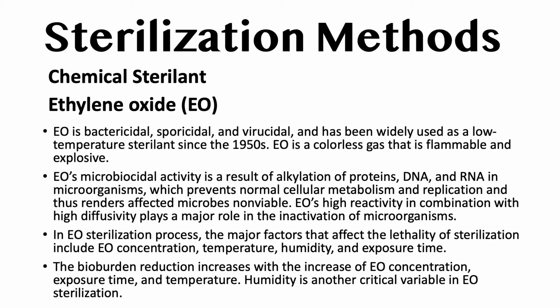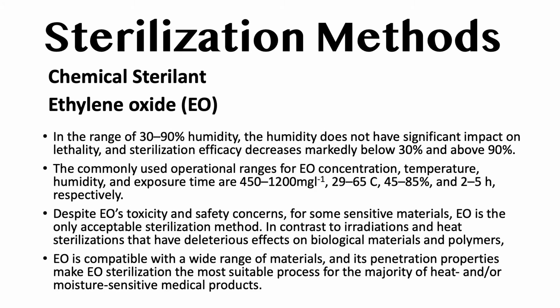In the ethylene oxide sterilization process, the major factors that affect the lethality of sterilization include ethylene oxide concentration, temperature, humidity, and exposure time. The bioburden reduction increases with the increase of the ethylene oxide concentration, exposure time, and temperature. Humidity is another critical variable in ethylene oxide sterilization. In the range of 30 to 90% humidity, the humidity does not have a significant impact on the lethality, and sterilization efficacy decreases markedly below 30 and above 90% humidity.